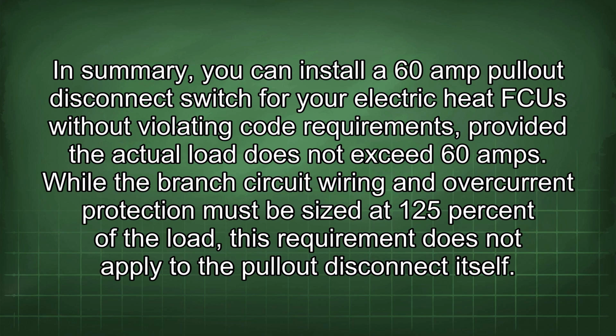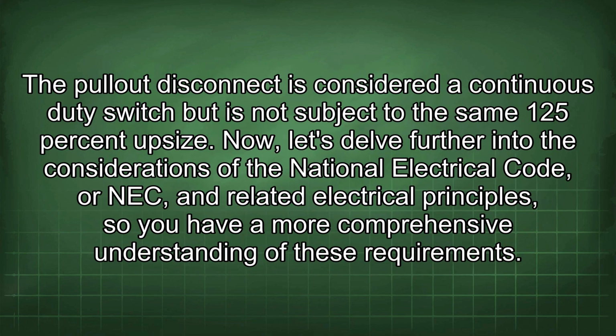While the branch circuit wiring and overcurrent protection must be sized at 125% of the load, this requirement does not apply to the pull-out disconnect itself. The pull-out disconnect is considered a continuous duty switch but is not subject to the same 125% upsize. Now let's delve further into the considerations of the National Electrical Code, or NEC, and related electrical principles so you have a more comprehensive understanding of these requirements.